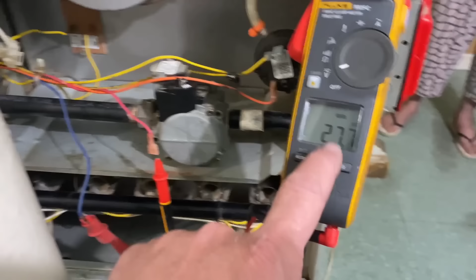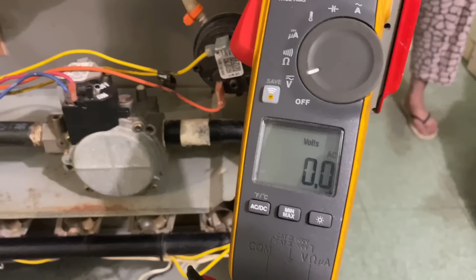27 volts to the gas valve. So we are getting power to the gas valve. Next is, why are we not getting any glow on our hot surface igniter? All right, we disconnected the Molex connector going to the hot surface igniter. So this is going from our control board. And the multimeter is set to read voltage still. Turn power on. Inducer motor will come on. And let's wait. There it is. So we're getting 113 volts.